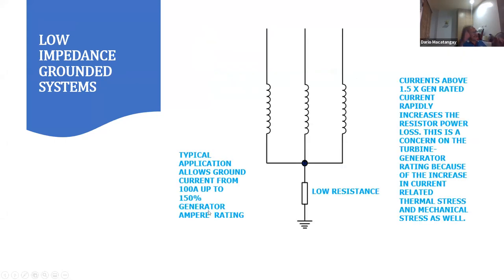So what we're saying is this is a low resistance on the neutral, okay? As you know, the zero sequence network has a very low zero sequence impedance if you have a low resistance on the neutral. So when you have this, the current is higher.